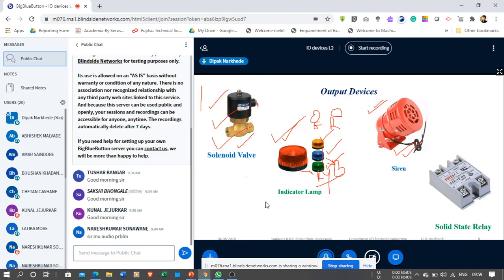Or you can control this amount by using timing also. But if you want to go for timing, you need to do multiple calculations. In case of timing, when my hopper is completely filled, initially the flow rate will be high, but as the level in the hopper decreases, the flow rate reduces. If I use timing for filling these milk pouches, it might be possible that initially the pouches might be 200 ml or 500 ml, whatever the quantity you want to fill in that.